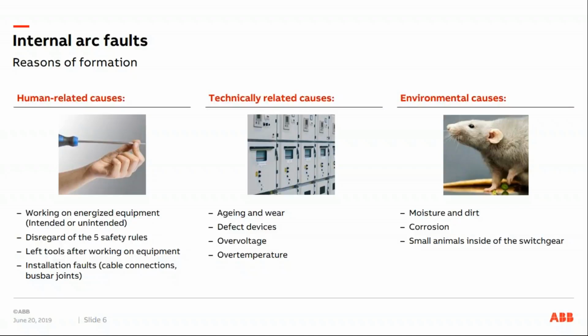Left tools after working on equipment, installation faults such as in cable connections or busbar joints. Another reason could be the technically related causes such as aging and wear, defect devices, over voltages, over temperatures, or environmental causes, which can be moisture and dirt, corrosion, small animals inside of the switchgear.